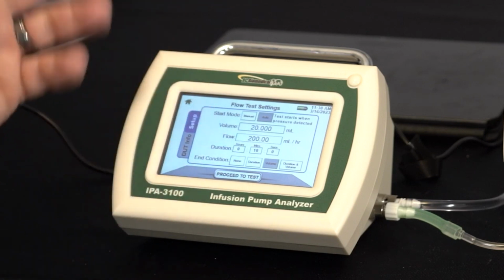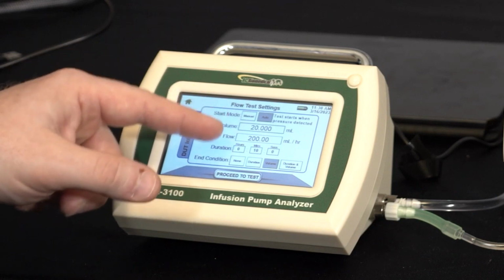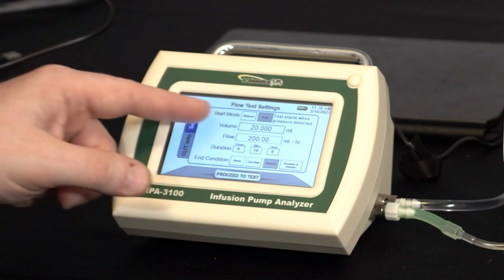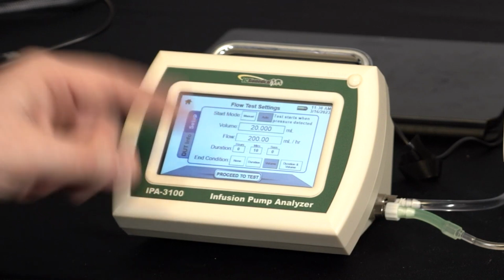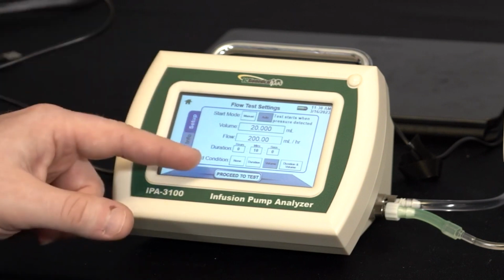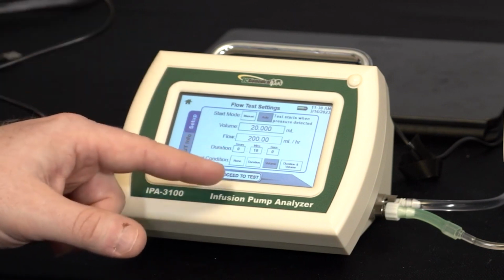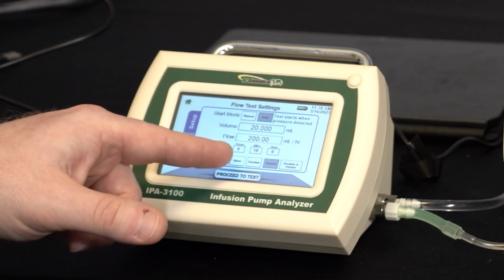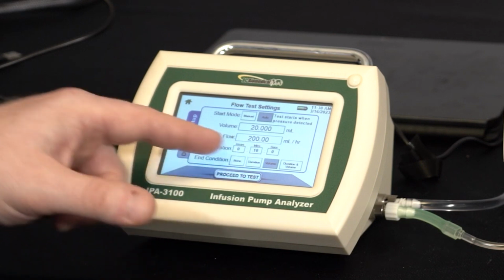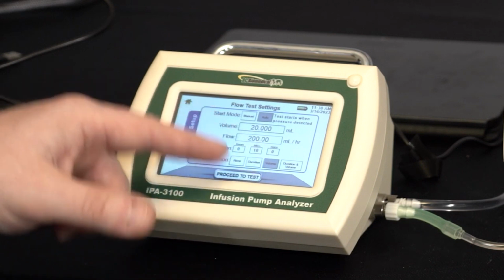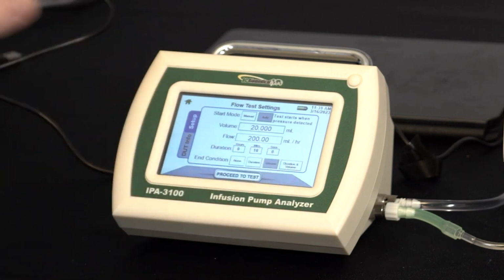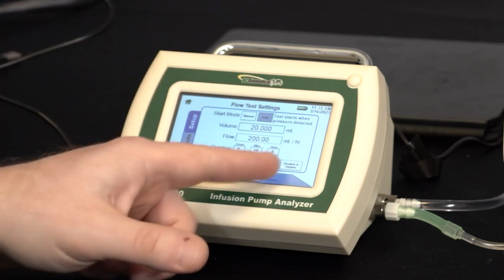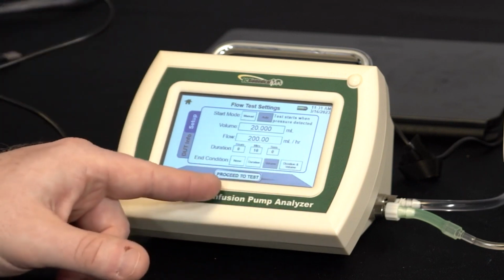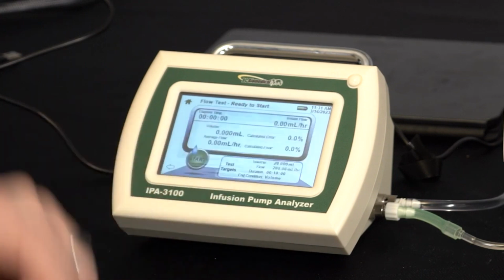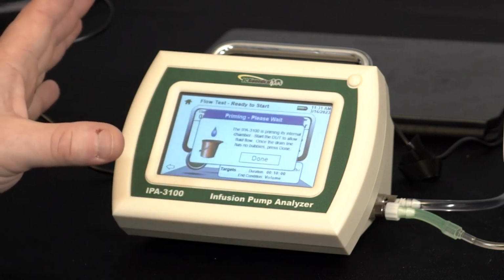The flow rate is the expected flow rate. These are used for calculating percent error. And then the duration is how long we think the test should run. So we can pick our end condition to be either manual stop, or based on the duration that we programmed, the volume that we programmed, or duration and volume. It has to meet both conditions. So I'm going to set it to volume just to be able to run our test. We hit proceed to test, and now it's ready to go.